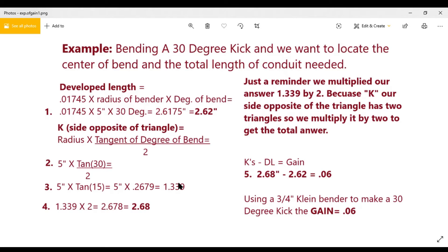For starters, let's use an example. For the sake of this video, we're going to say we're bending a 30-degree kick with a three-quarter pipe using a Klein bender, and that bender has a radius of five inches. If you're asking how I got that number, go back to video one — it'll show you how to get the radius of whatever bender you're using, because keep in mind that all benders are not equal.